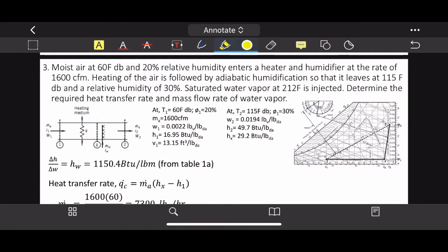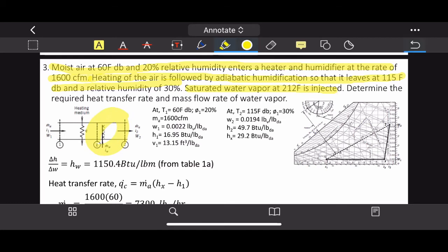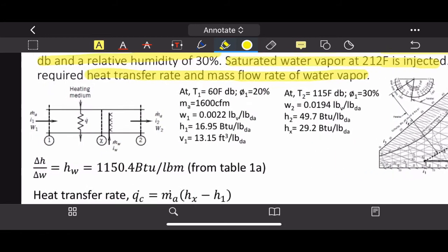Question 3 uses English units. Moist air at 60°F dry-bulb and 20% relative humidity enters a heater and humidifier at 1600 cubic feet per minute. The air is first heated, then adiabatically humidified, leaving at 115°F and 30% relative humidity. Saturated water vapor at 212°F is injected for humidification. Determine the required heat transfer rate and the mass flow rate of the water vapor.